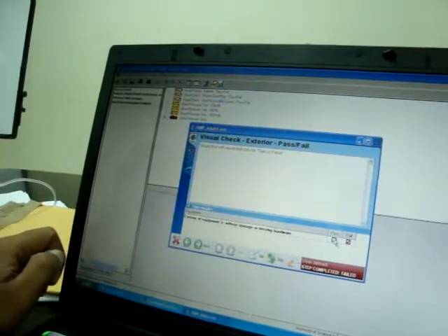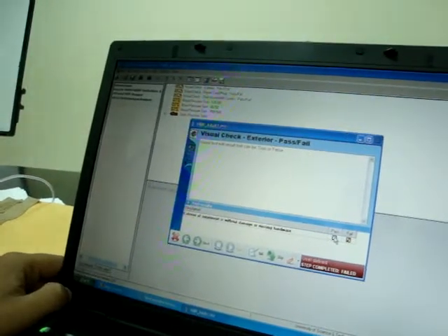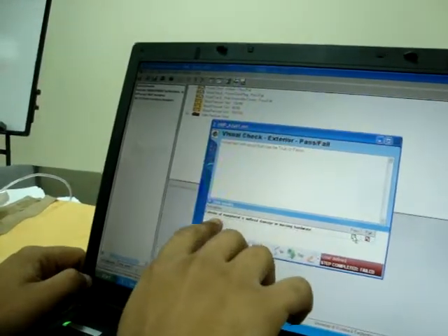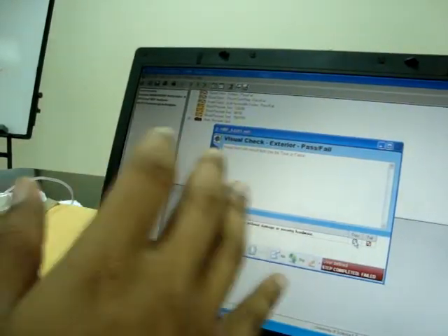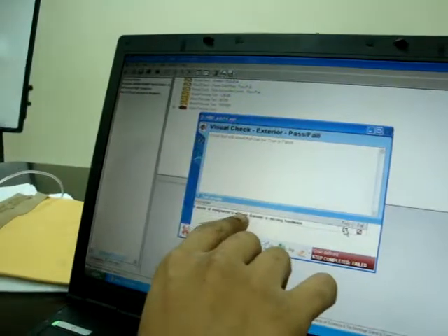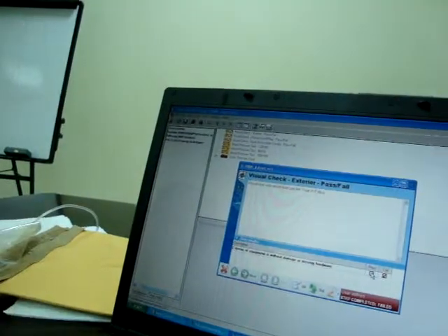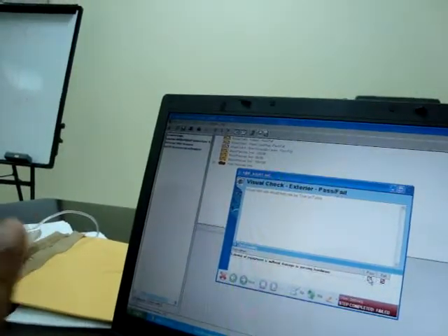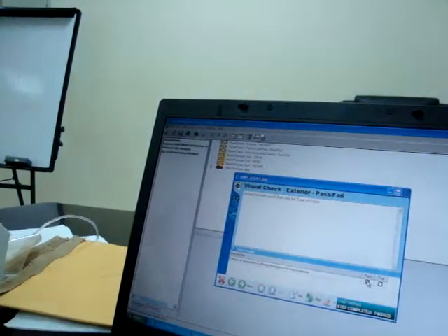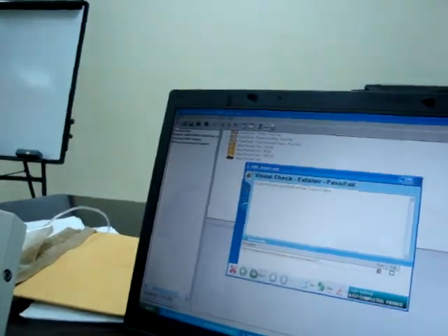Okay. But how do you know the equipment is pass or fail? See, exterior of equipment, this is not the full test. This is just one step. First step. If this is the BP pump, it's asking whether the exterior of the equipment is okay. No breakage, nothing. Exterior means external. Okay. Click next.